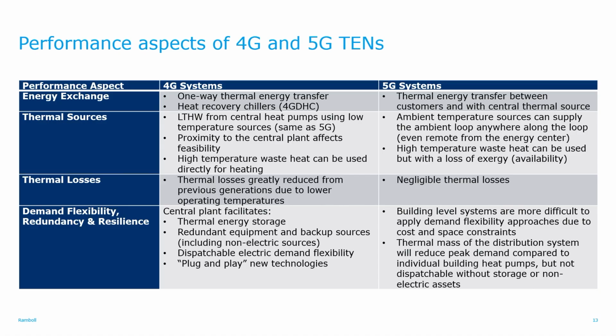Now note that 5G, since it's a thermal source network with an ambient temperature, can accommodate the addition of thermal sources anywhere along the loop. With 4G, you need to bring that low temperature, low grade heat to the central plant first.